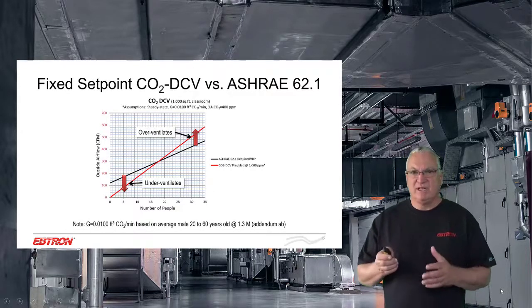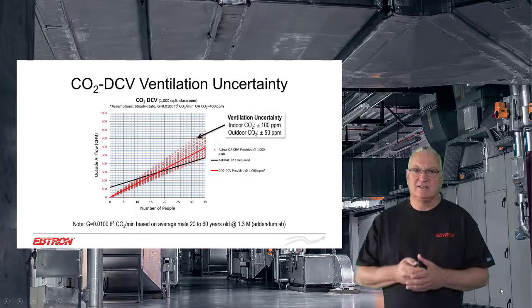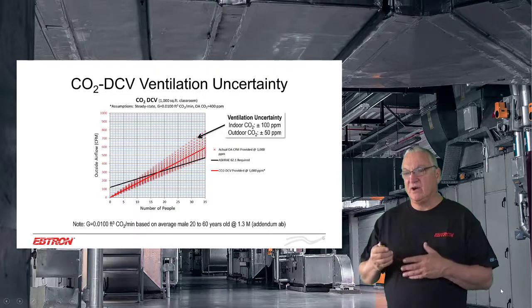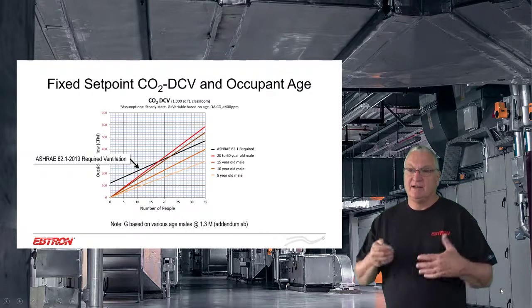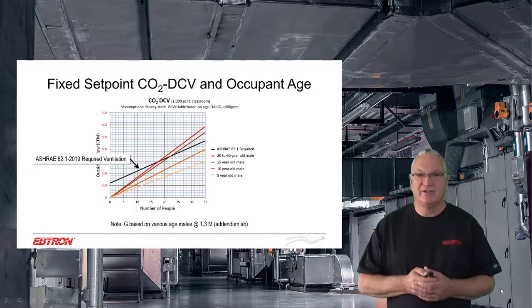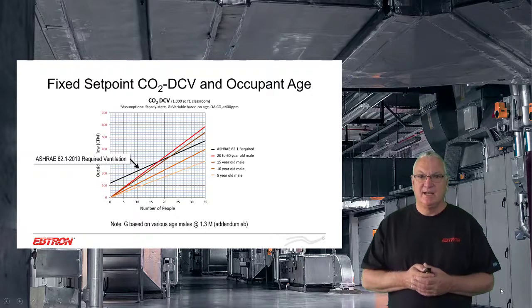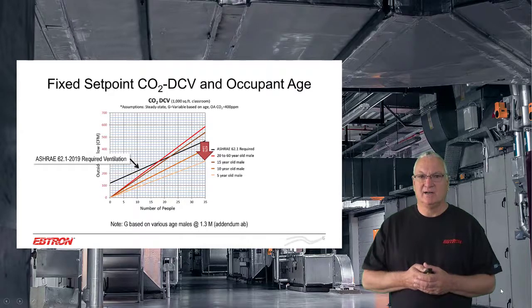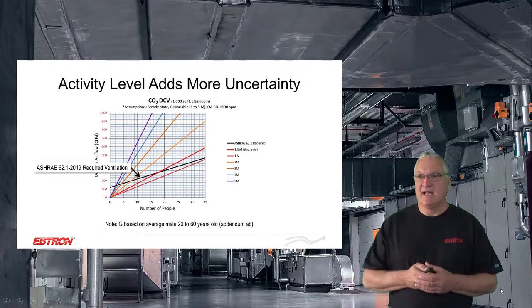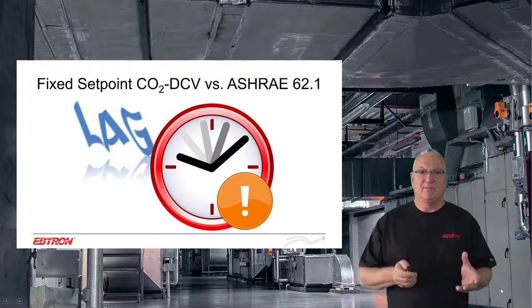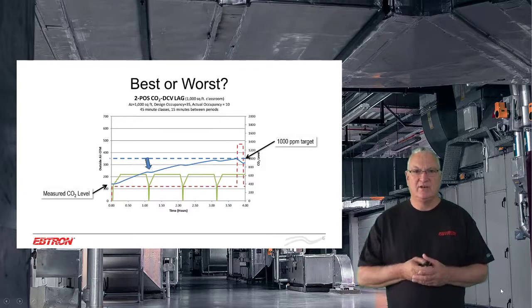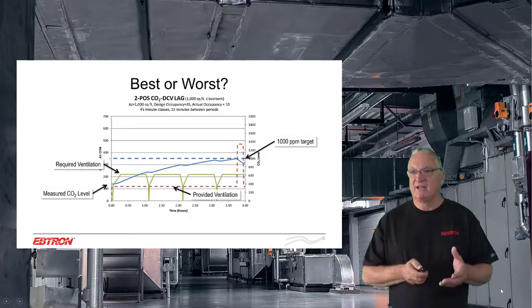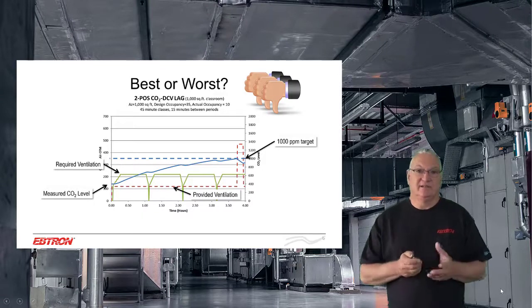We'll look at how CO2 control doesn't even meet the requirements of the ventilation standards, and how these uncertainties affect how much outdoor air you're actually bringing in. The relationship between CO2 and ventilation is dependent on CO2 production rates, which is very age-dependent. We're going to show you how some schools where you think it's safe are really under-ventilating by doing CO2 ventilation control. We'll talk about activity level and how it has to be taken into consideration. One of the big problems is lag — low CO2 levels don't necessarily mean you have proper ventilation.